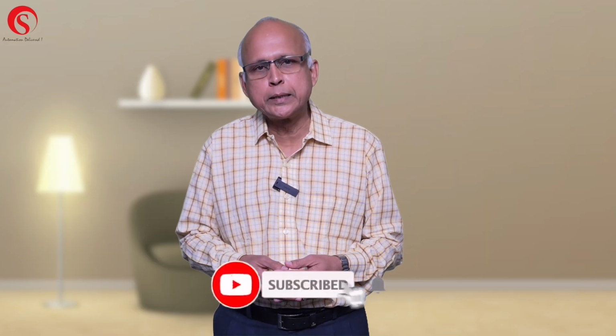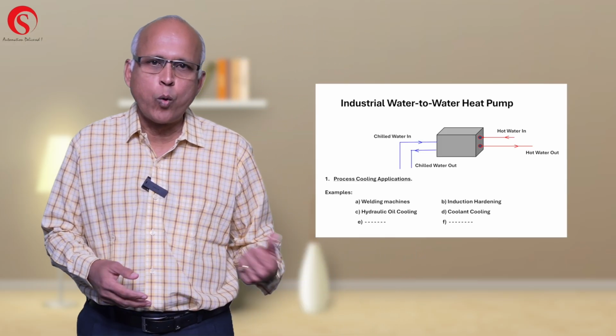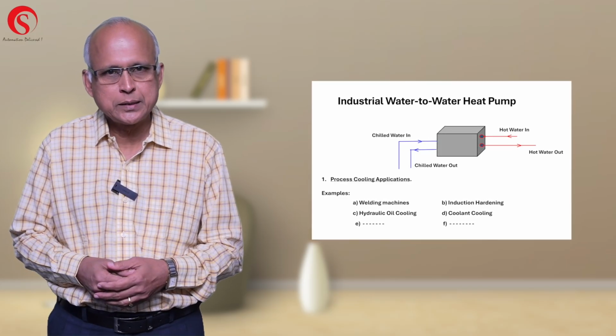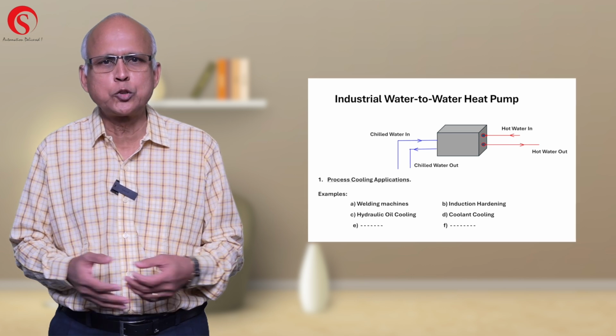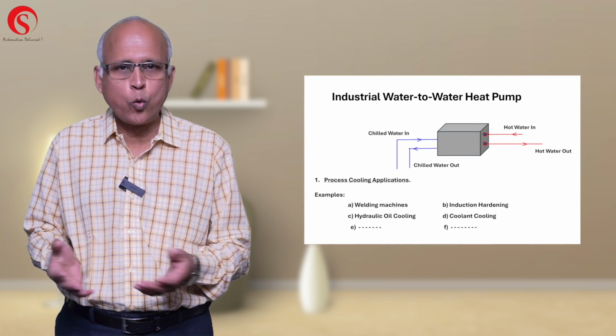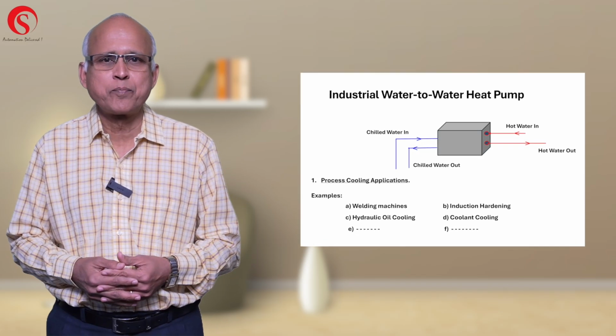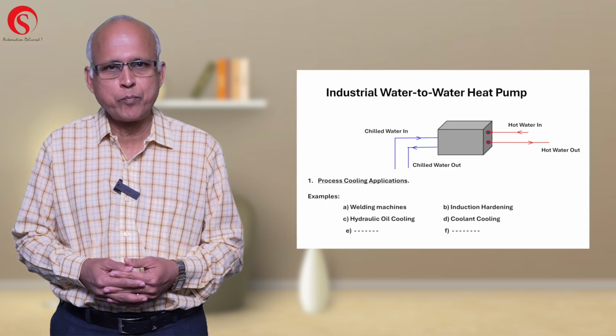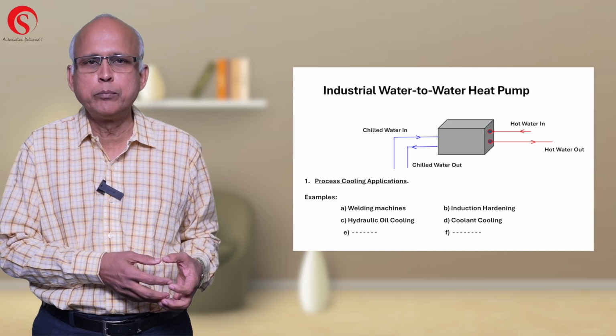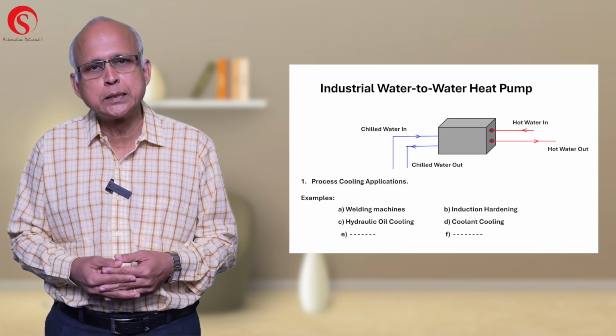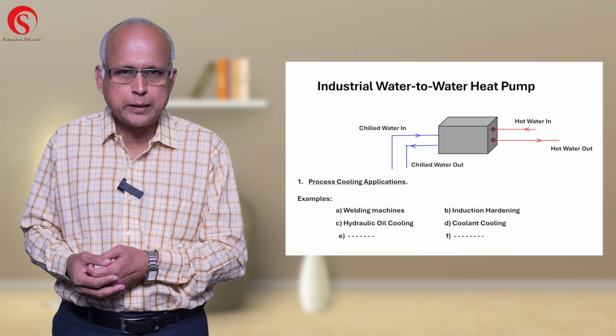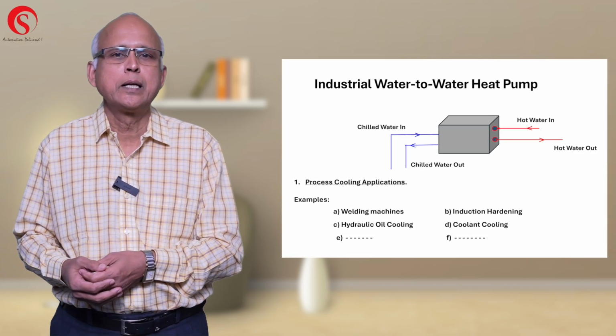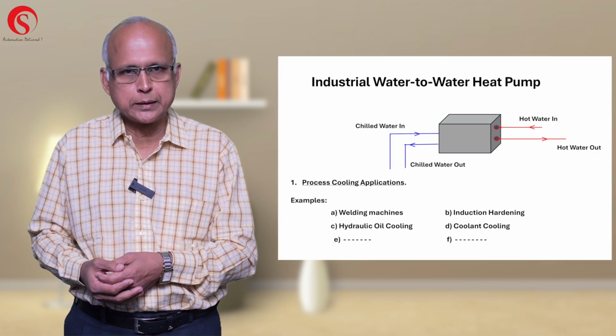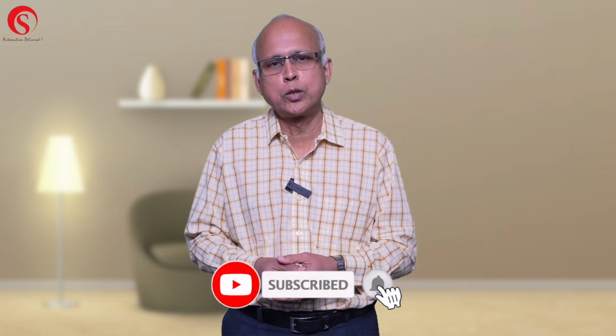Now looking at industrial applications, I generally see two types of opportunities for the generated chilled water. One is for process cooling applications, like on your typical shop floor, there are so many hydraulic oil cooling units, coolant coolers, induction hardening chillers, laser welding machine coolers, etc. The chilled water generated from the heat pump could be used for some of these applications. The second opportunity I see in industries for the chilled water generated is for thermal comfort air conditioning systems. First we will discuss both of these types of applications. Let us start with the process chiller application.